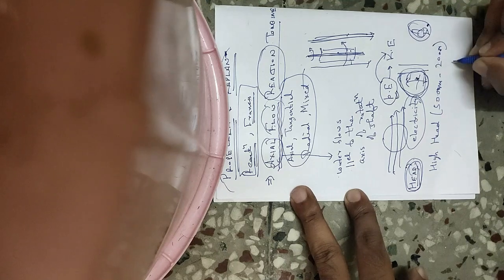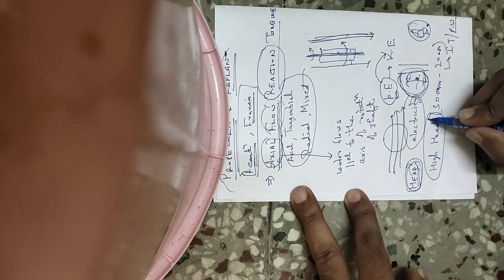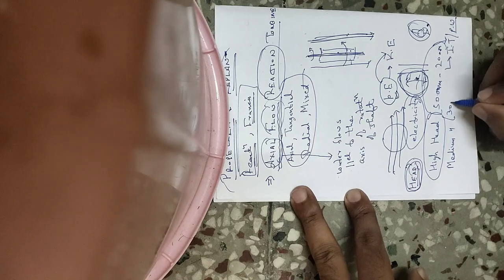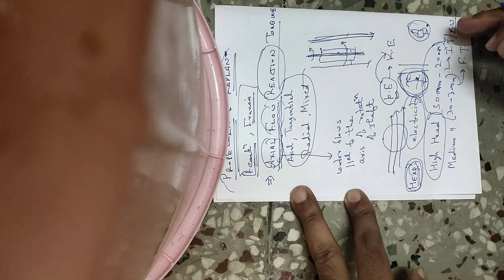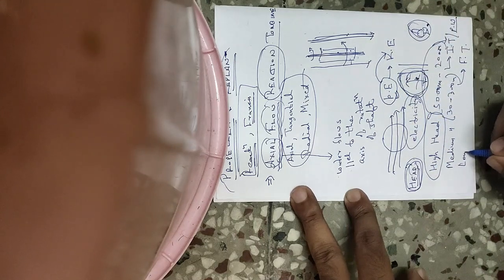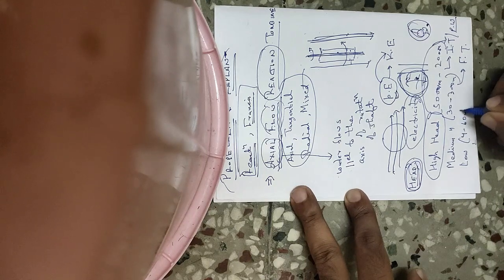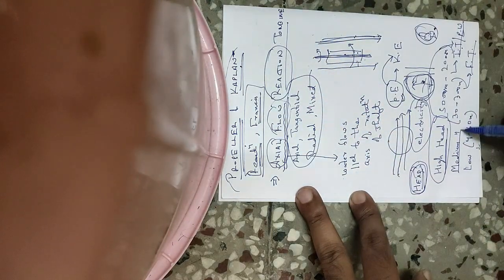For a high head system — say 500 to 2000 meters — you use an impulse turbine or Pelton wheel. For medium head — around 30 to 300 meters — you use a Francis turbine. For low head — around 4 to 60 meters — that is where propeller and Kaplan turbine come in.